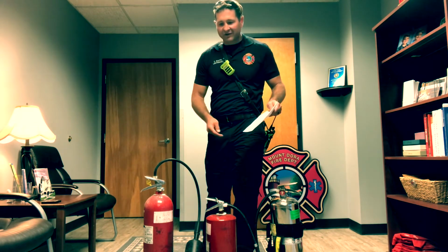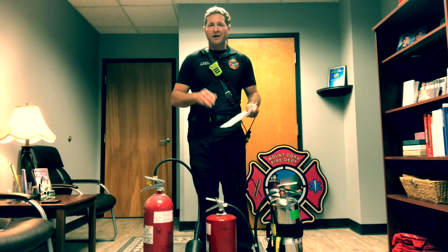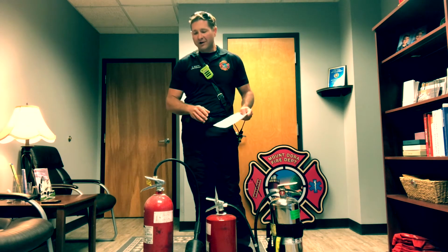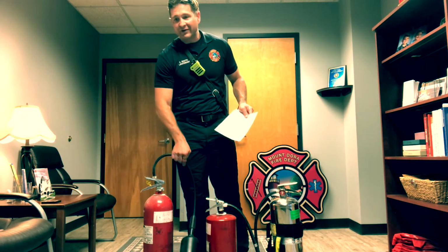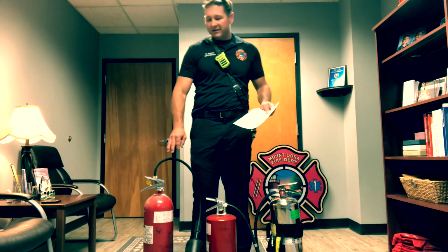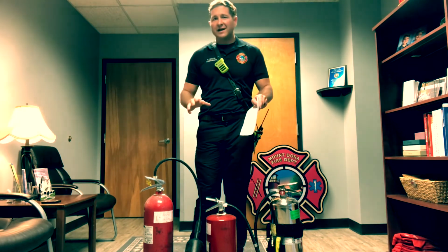The ABC extinguisher acts by interrupting the chemical chain reaction, as well as smothering a fire so that it deprives it of oxygen and cannot burn any longer. A CO2 extinguisher functions in a similar way by smothering the fire, but it is most appropriate for energized electrical equipment, as it doesn't leave any residue behind in order to gum up or damage any equipment.